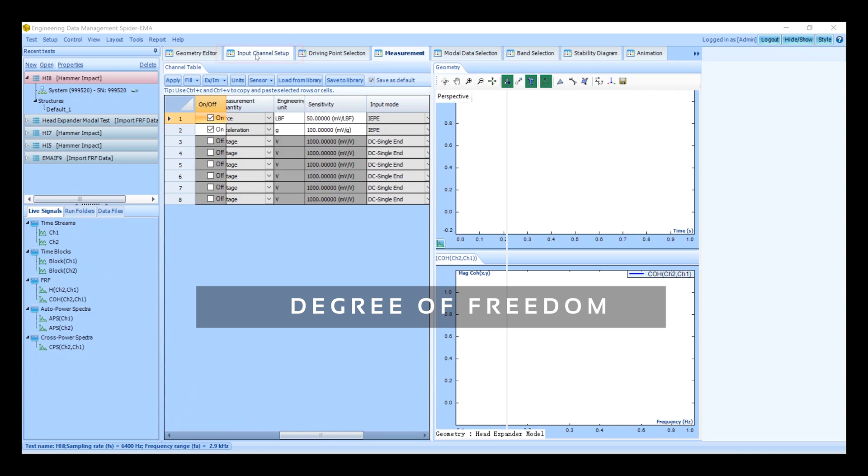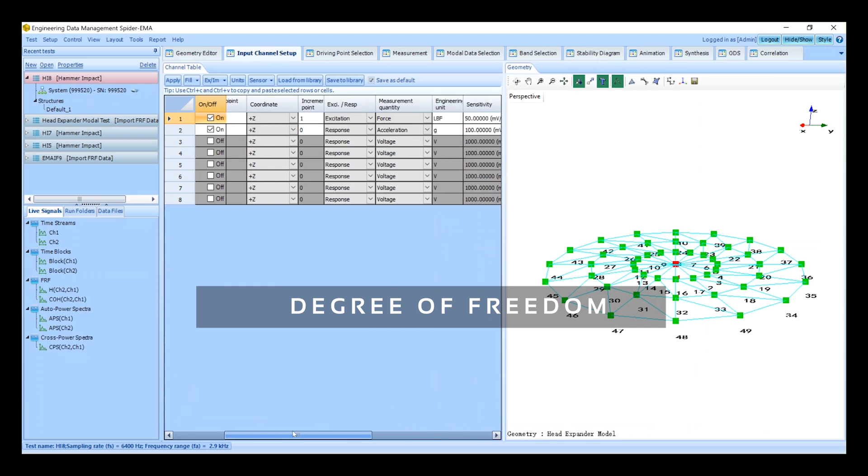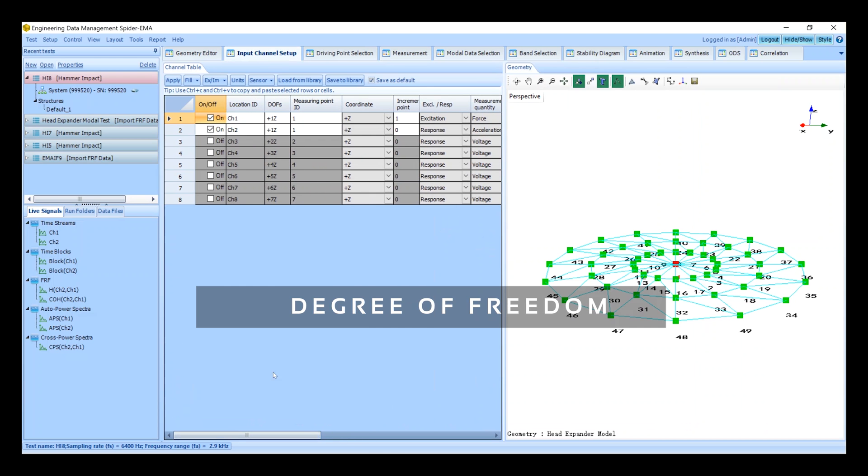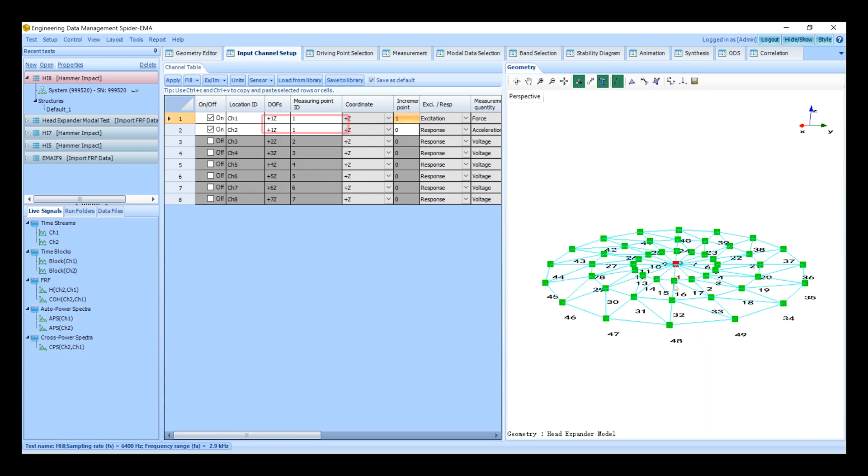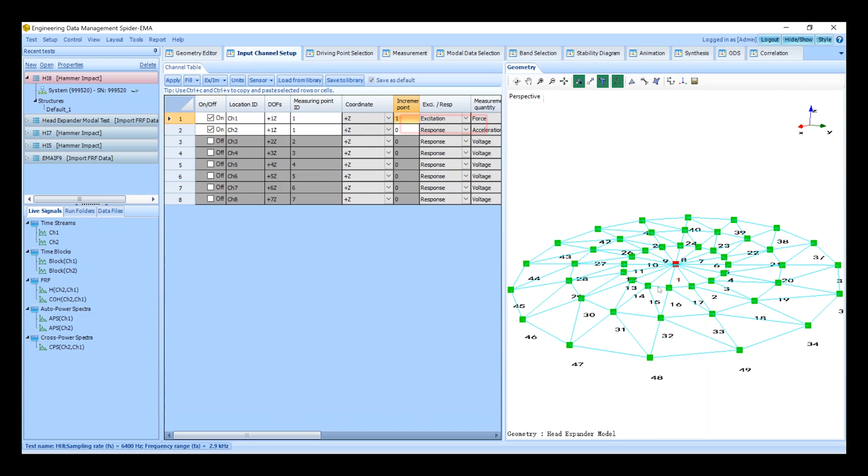Now return to the input channel setup to configure the DOFs. We must assign a measuring point ID and an increment point for each channel. Since this is a roving excitation test we must ensure that the excitation channels are always assigned to the appropriate points on the structure. The measuring point ID represents the DOF point number. Since we will start at point number one we need to choose this number as the measuring point ID for our excitation channel.